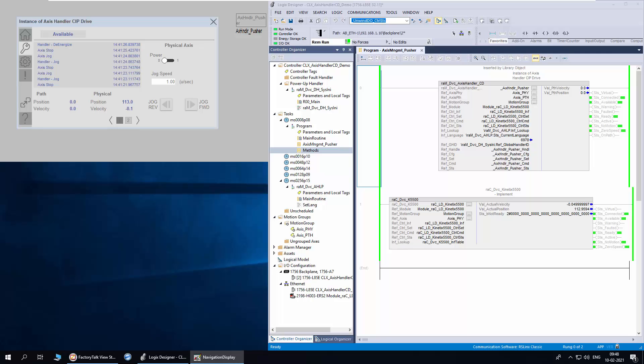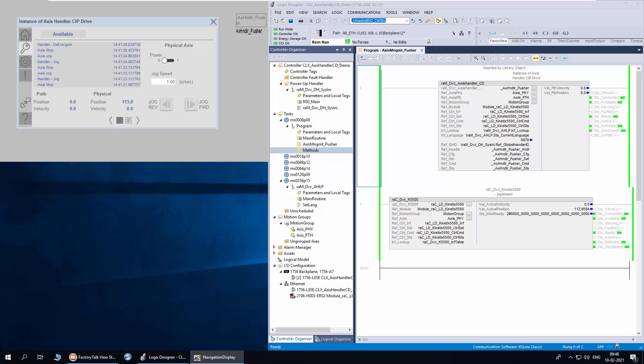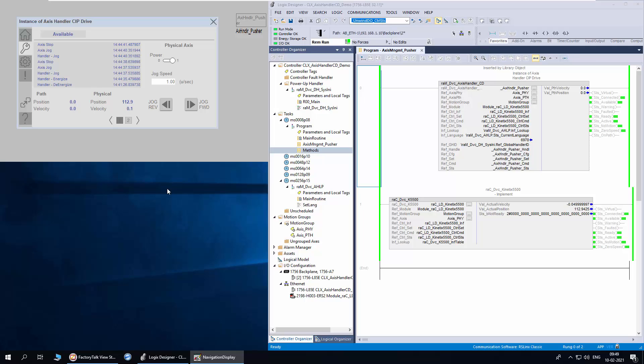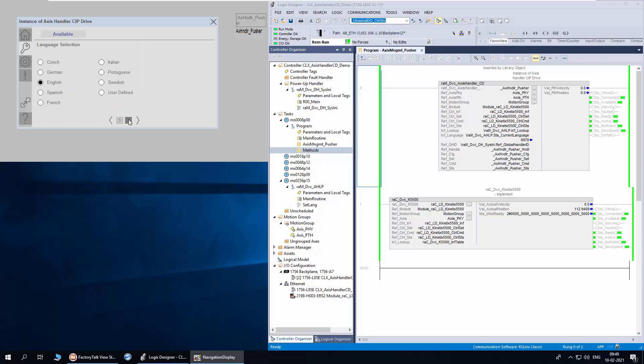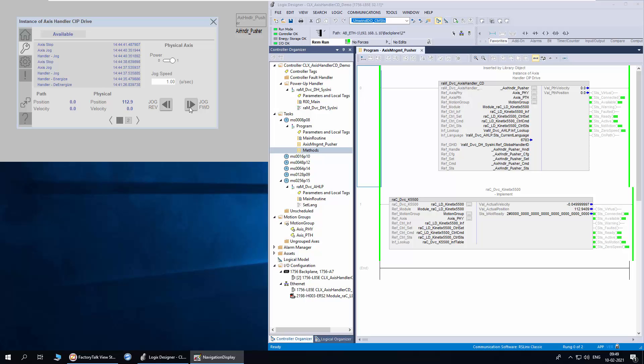To demonstrate the language pack, I have enabled the motion status to be captured in the event list. First, I will jog the axis and show the motion status events in English language. You can see the motion status axis jog and axis stop are captured in English language. Next, we will switch the language to Czech. A language can be selected only if it has been included when instantiating the language pack object in ACM. Now I have selected the Czech language. I will go back to the jog page and again trigger the jog forward button. Now you can see the axis jog and axis stop motion status are displayed in Czech language.